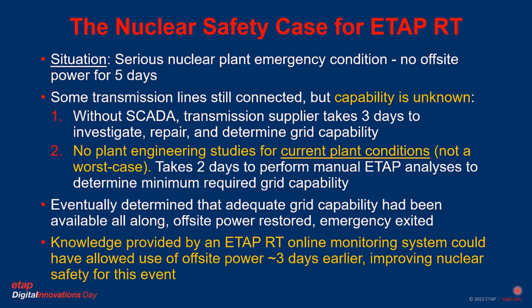And the bottom line, without getting into too many of the details for this particular presentation, is the knowledge provided by an ETAP real-time online monitoring system could have allowed us to use offsite power about 3 days earlier, because it was actually capable all along. But without the transmission line SCADA system and without our normal ability to determine the adequacy of the grid, we didn't have any built-in plant engineering studies for the current plant conditions that we found ourselves in, because it was not a worst case. And this would have improved nuclear safety for the public had we known that we had offsite power available about 3 days earlier.